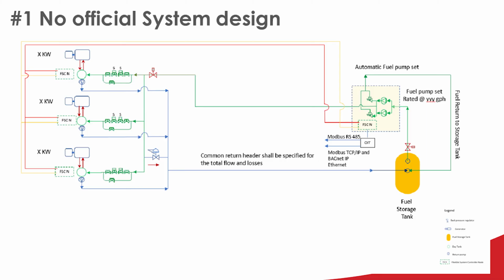A defined control strategy is critical. Most of these components have sensors, starters, and valves that need to be synchronized and work in harmony in order to deliver the fuel in an adequate manner. To give you an example, is the main fuel pump interconnected with the day tanks, main tank, and safety interlocks? If your day tank overflows, will you be able to stop the main pump set from running?